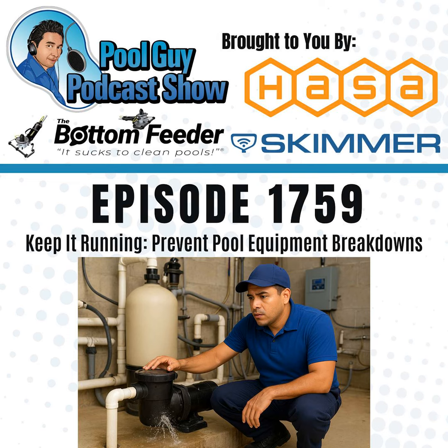It can also leak from the seal plate gasket. I find this to be very common with certain pumps. Other pumps, you never have a leak at the seal plate. I find that the Super 2 pumps by Hayward always have a problem with the seal plate, especially when you take off the motor and try to put it back together. But a lot of pumps don't really have this problem. I've had pumps leaking from the drain plug. Now, for the drain plug on the pump, there's actually an O-ring on there, so change that O-ring if necessary. Usually, the leaks are solved by changing an O-ring on there, or changing, of course, the pump seal in the case I mentioned earlier. But the O-rings wear out along with the pump itself as it gets older.